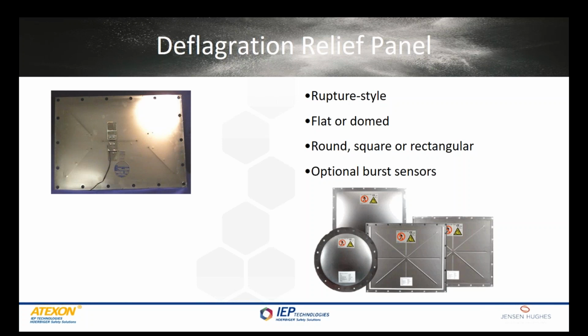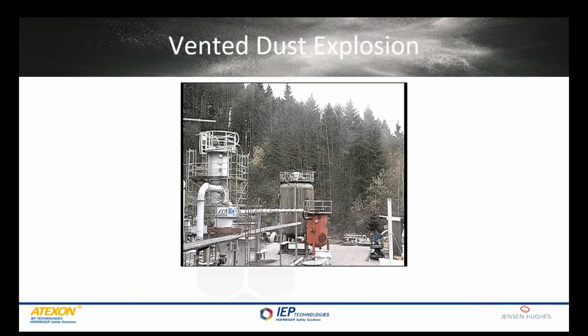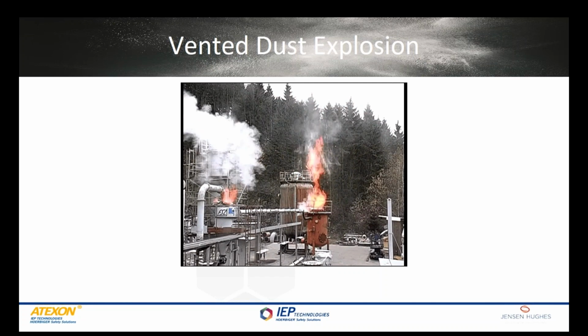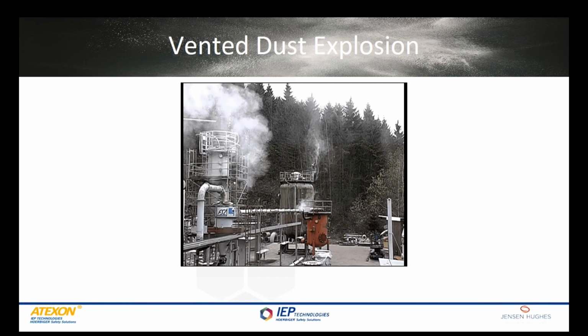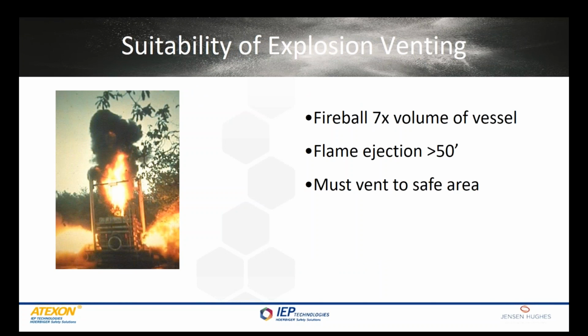Since explosion venting is generally the least expensive means of protecting a vessel, it's always preferred when possible. So when can explosion vents be used? We need to remember that when an explosion vent is being used, you are releasing a very large fireball to the outside, in a controlled manner, through a specific opening within the process. Oftentimes, that vent will relieve a fireball that could be 7 to 8 times the volume of the vessel. And it doesn't come out in a nice round sphere. It comes out in a flame jet that can eject 50 feet or more. I remember doing a recent vent calculation in which the flame ejection distance was 134 feet. So you could see a very, very long flame ejection distance.